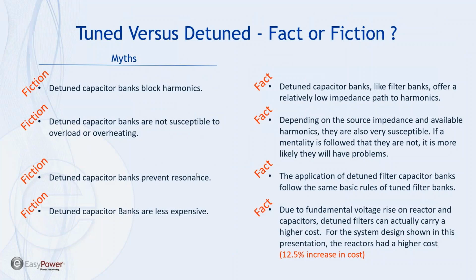So tuned versus detuned, fact or fiction. I talk about the myths and I talk about the facts. Detuned capacitor banks block harmonics. That's fiction. Detuned capacitor banks, like filter banks, offer a relatively low impedance path to harmonics. This is actually impacted by the source impedance. The higher source impedance means that both filters will take in higher levels of harmonics. The question is, how much?